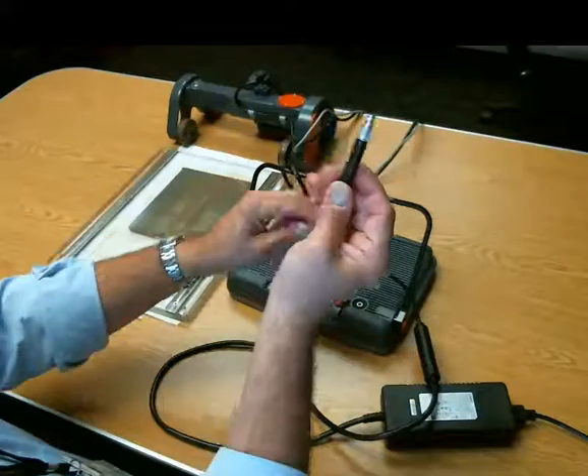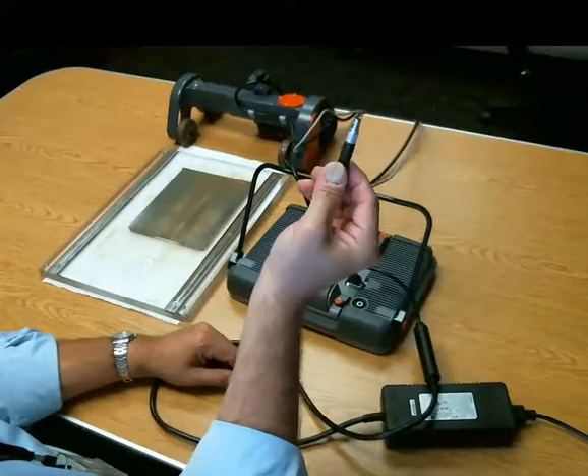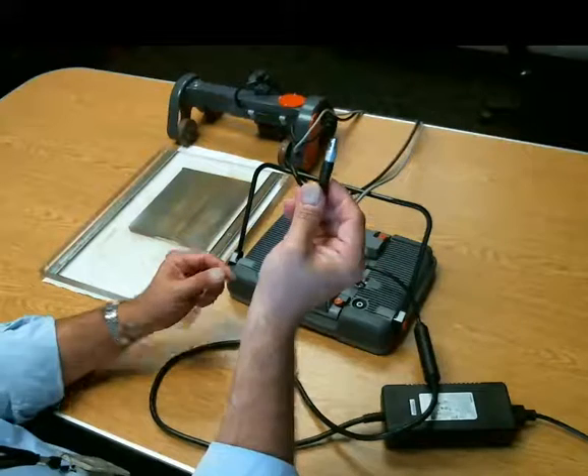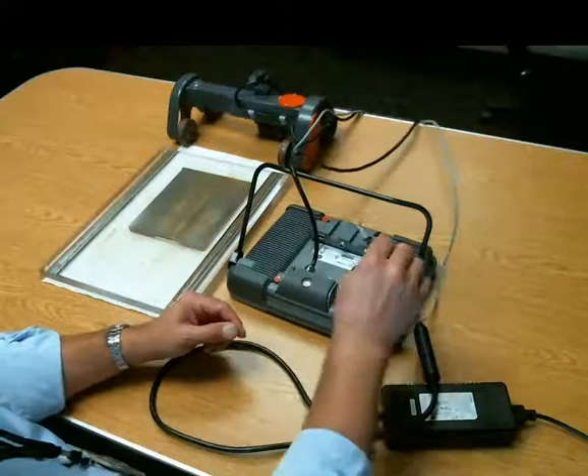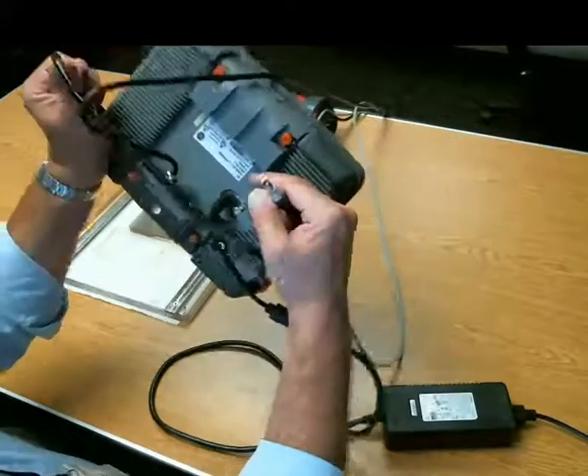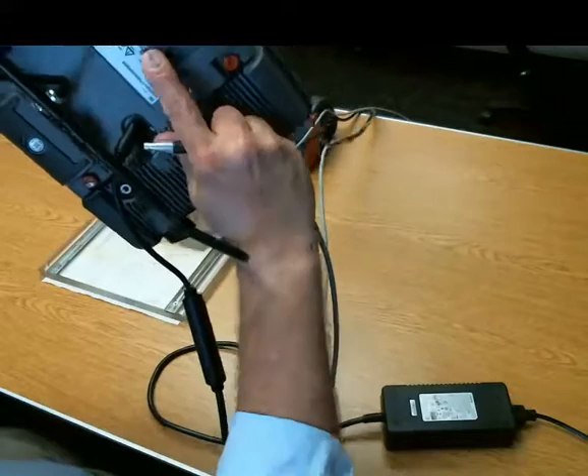The other cable is the encoder. So we have two axes of mechanical quadrature encoder in the scanner. You want to plug this connector into the XY connector. If you look closely at the back at the module, one of the connectors is labeled XY, the other Z.